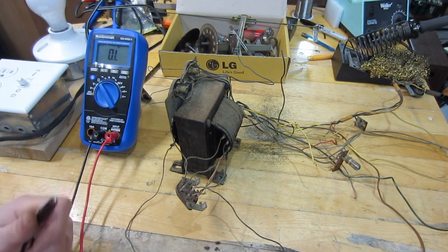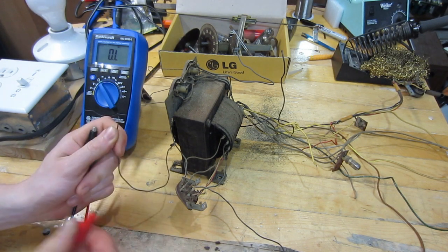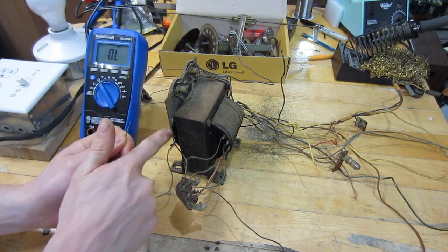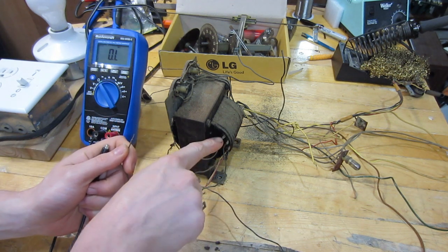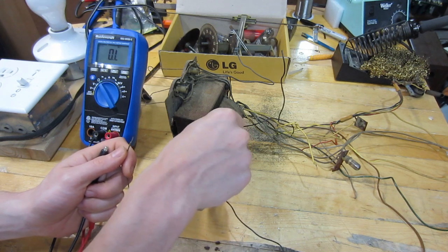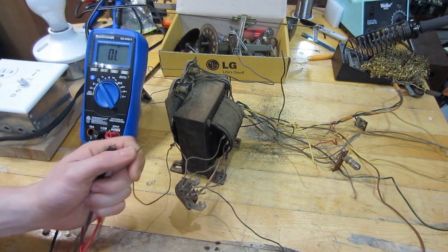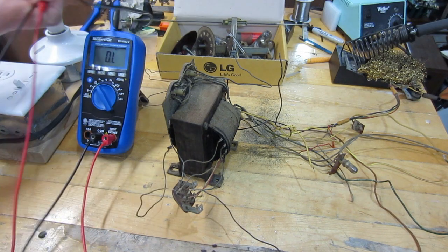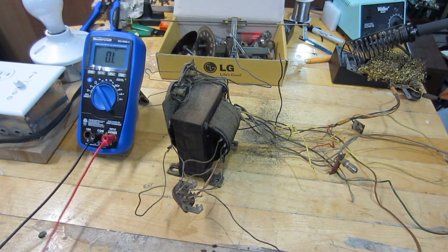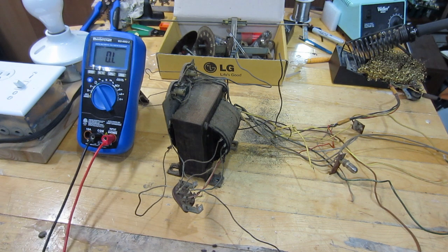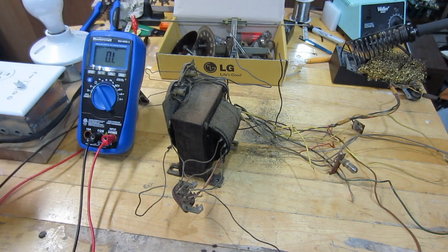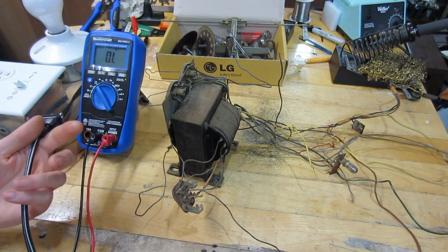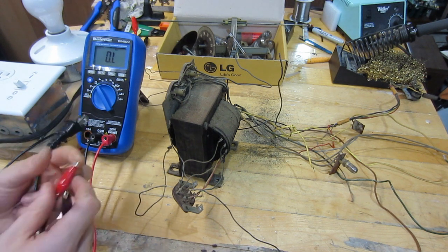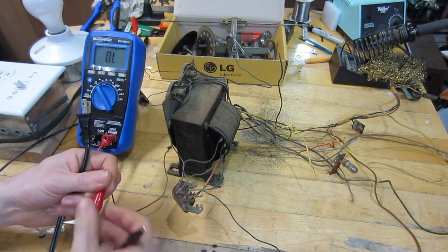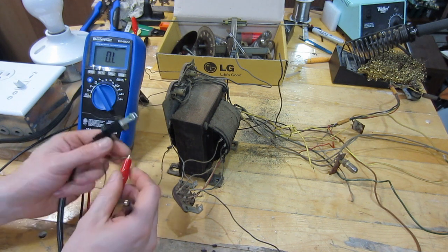So now that we've determined where our common is and which winding we want to use - probably this one here, which is 125 - that will be our second tap. The other ones are for 220, 240 volts. So if you're in a European country, this transformer is perfect because it's universal, right? That's actually what I like about these transformers. So let's see, our neutral is this wire.